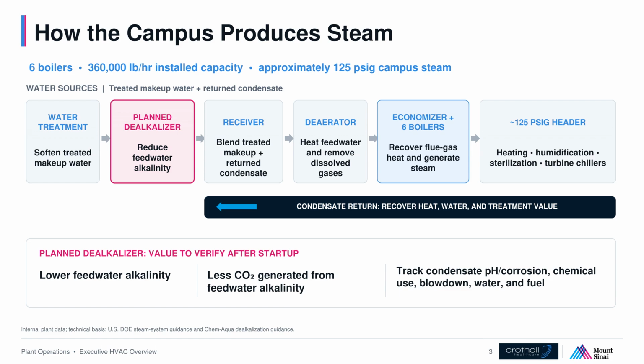Condensate return is not waste plumbing. It recovers heat, water, and treatment value. And the dealkalizer is not a savings claim. It is a testable hypothesis. Lower feedwater alkalinity should generate less carbon dioxide from that alkalinity, which may improve condensate conditions and reduce chemical use, blowdown, makeup water, and fuel. But measure before promising. Establish a baseline, commission the equipment, trend condensate acidity and corrosion, and compare treatment, blowdown, water, and fuel after startup. The engineering lesson is simple. Verify the whole steam and condensate system, not just the new vessel.